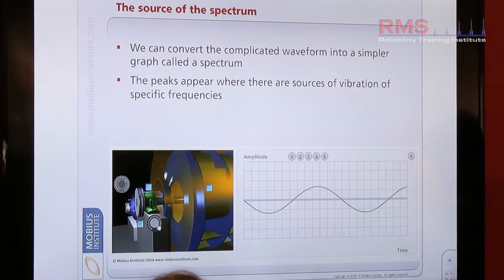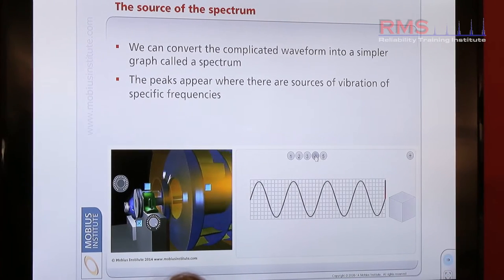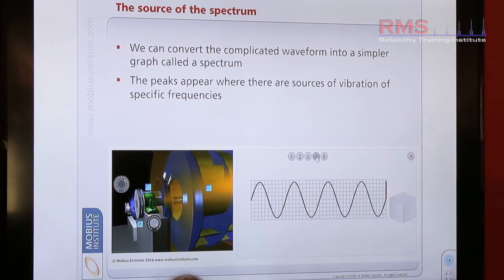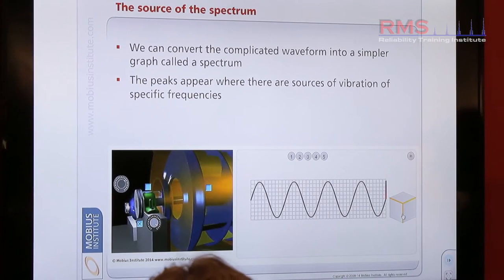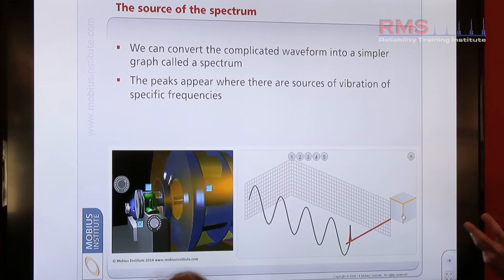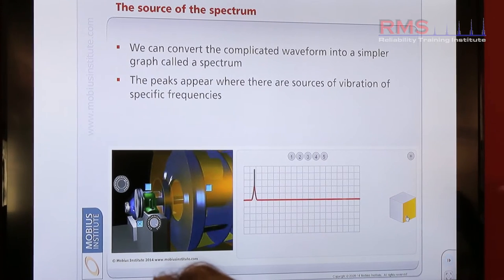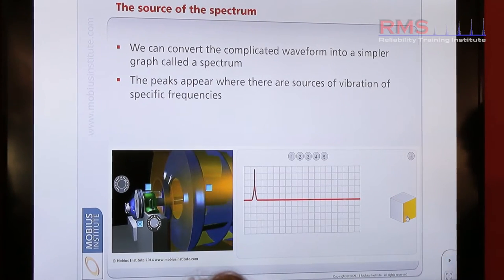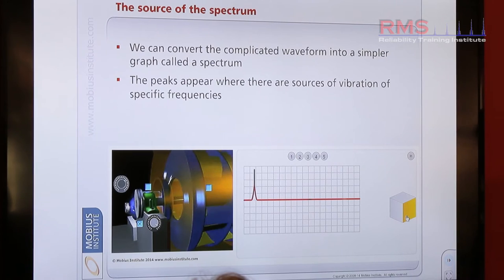So what do we do? Well, that waveform is very complex. Let's make it easier. Here's the wave. I'm looking now at that signal. I'm looking 90 degrees at that signal — what do I see? The end of the wave, a line, a peak. In simple terms, vibration systems today take the signal initially and convert it to a frequency spectrum. If I initially upturn that 45 degrees, and then complete the 90 degree rotation, what do we see? One single peak. So we take the time wave and convert it to a frequency peak — a very crisp, sharp way of presenting the data. This peak here would be proportional to rotation speed.